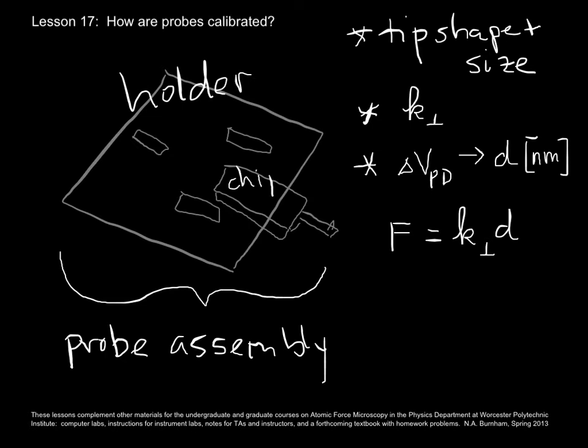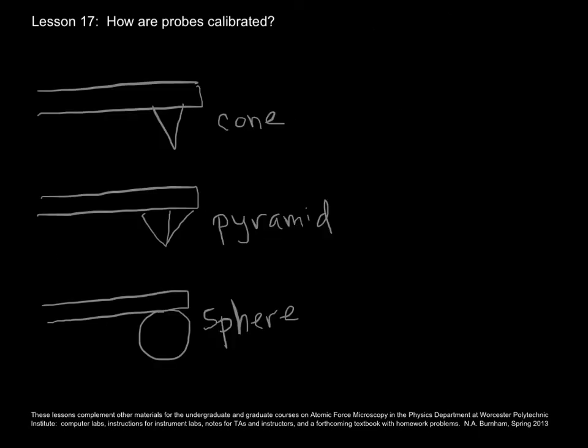This part here that you grab with the tweezers, I call the cantilever chip, or the probe chip. Here, this is the cantilever, that's the beam. It's rectangular, sometimes triangular, and here is the tip. So when you refer to an AFM tip, that is just the end of the cantilever that is in contact with the sample, or coming close to the sample, and perhaps briefly touching it in a dynamic mode. Tips usually come in three shapes: cone, pyramid, or sphere.